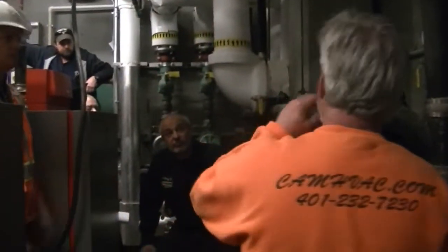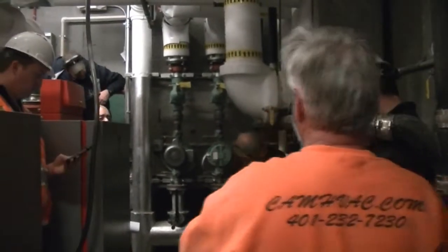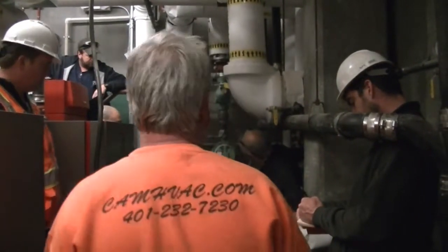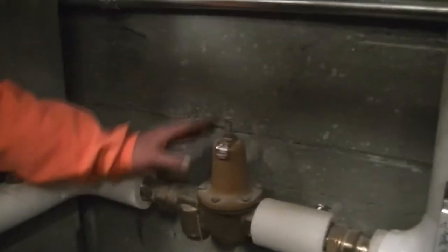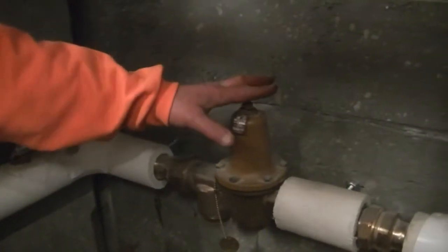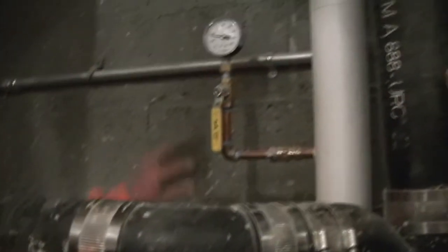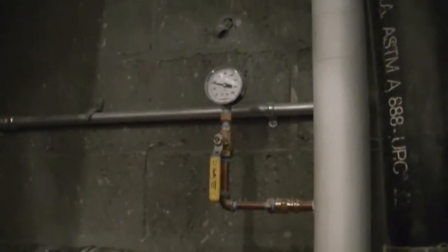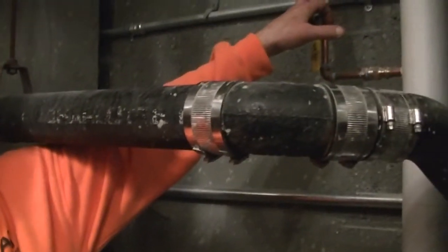Okay? Maintenance on those pumps, there is none. Those are maintenance-free motors. You basically just have to make sure they're kept clean. Okay? Over here, we have your pressure reducing valve, which is your water makeup for the system. All right? So this is set at around 23 to 25 pounds. So if for some reason the system needs water, it'll make it up on its own. If it has to make up water all the time, you get a problem. Don't be surprised if this is reading higher than what this is set at after the system heats up. This is set for your cold water temperature to make up water. Once the boiler fires up, water expands. Okay, this stops filling. This valve can definitely climb to 40 psi, which is what it's done.